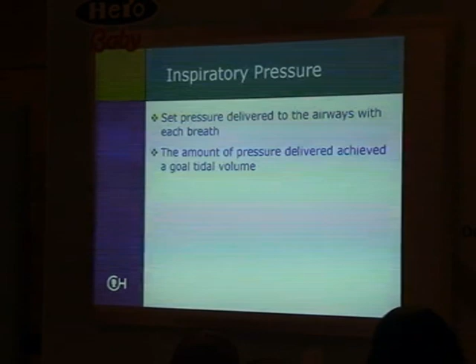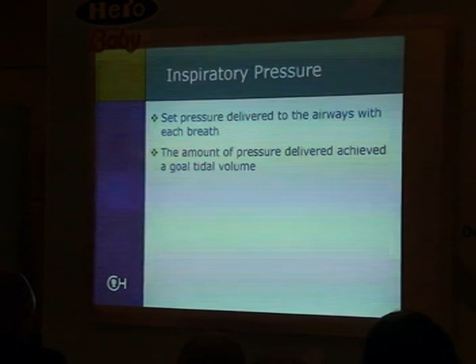Next is the inspiratory pressure, and as I said, to me, this is one of the most important settings, making sure that it's set appropriately. And this is how much pressure you give during inspiration when taking that breath in. It's generally set in centimeters of water pressure, and then you'll get your volume that's delivered, and you want to make sure that you're monitoring that reading.